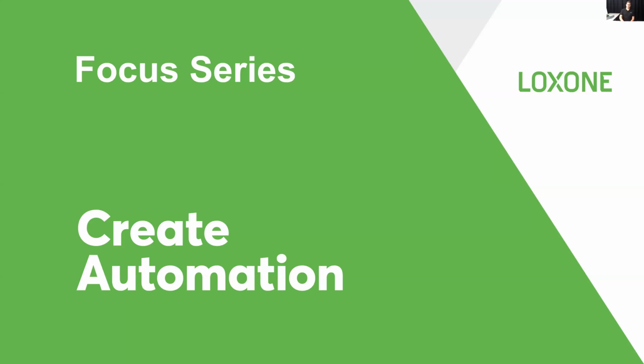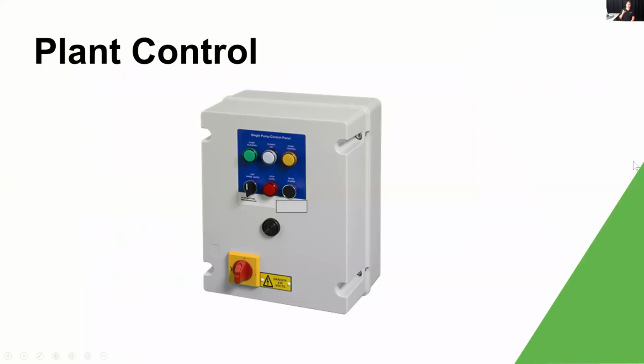Now our particular one that we're going to be looking at today is going to be around pump control. So in a lot of commercial buildings, you will quite often see something like that in a plant room, and that is a pump controller. Could be for a bilge pump, a sump pump, a circulation pump, doesn't really matter. But what we've essentially got on there, if you can just about see it, there's a black selection switch on the bottom left, and that will usually have written on it something like auto on off or hold on off. And what that essentially means is the pump is either completely off, it's completely on, or it's in an automatic mode, usually schedule based.